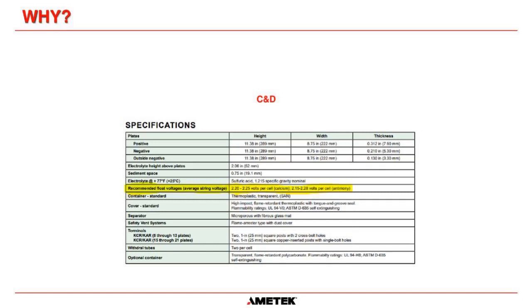For equalizing in vented lead acid cells, what about mitigating acid stratification? That's a good question, David. Battery manufacturers don't recommend that you equalize the batteries for acid stratification. They only recommend equalizing the battery for cells being outside their tolerance. IEEE may have some wording in there for acid stratification. Once again, that's just a recommendation. Equalizing your battery is not going to do any harm to your battery.